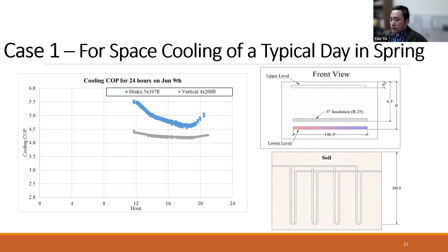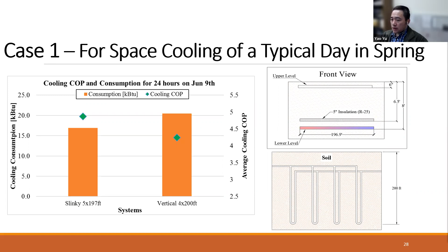And this slide shows the corresponding cooling energy usage of the heat pump, along with the daily average cooling COPs. The lower horizontal loops have lower energy usage due to the higher efficiency and colder underground regions compared to vertical ones. So this result shows that we can meet the space cooling demands in spring for this house by using a lower loop. Again, the idea of using the lower loop for space cooling in this season is to allow the transfer of some of the building heat to the lower underground regions, which is good for space heating in the coming winter.